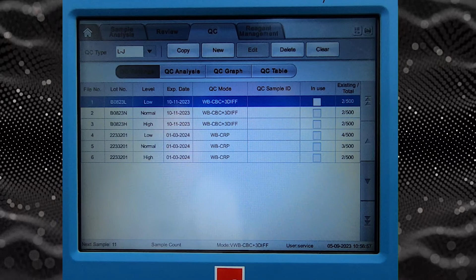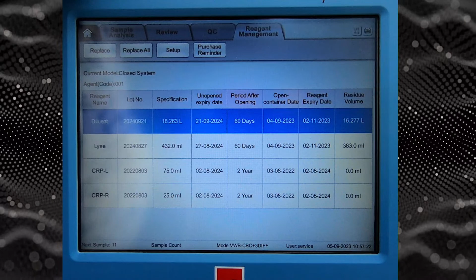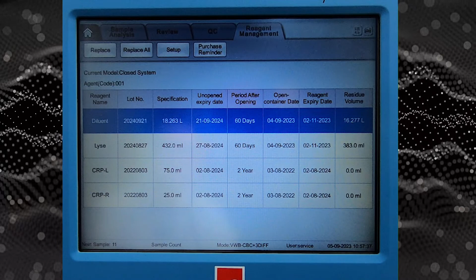Reagent management. As I said in my presentation, when you turn on the analyzer, you will need to go here, choose the reagent, and simply go to setup and use the RFID card. I think I have one here somewhere on the back. Use the RFID card and activate your reagents this way. For each reagent there will be a separate card, so you need to activate each reagent separately.